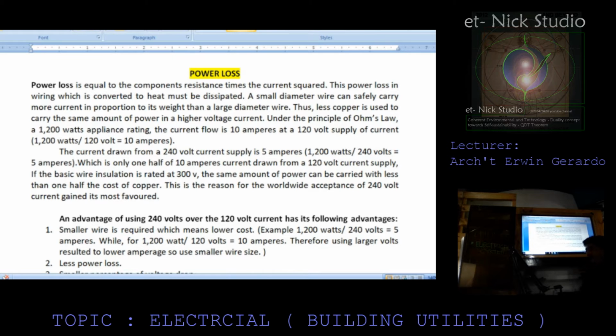Power loss is equal to the component's resistance times the current squared. The power loss in wiring, which is converted to heat, must be dissipated. A small diameter wire can safely carry more current in proportion to its weight than a large diameter wire. Thus, less copper is used to carry the same amount of power in a higher voltage circuit.